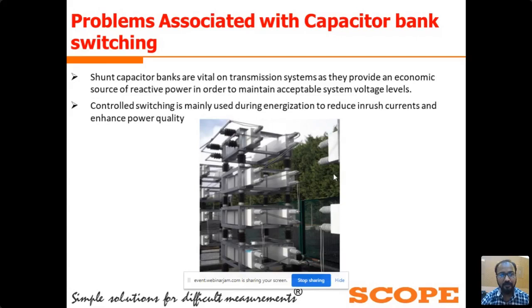During random energization of a capacitor bank, we have observed high inrush currents in the system. This type of high inrush current causes disturbance to the other connected systems, and also affects the power quality of the system. So to minimize this high inrush current during the energization of the capacitor bank, we are using the control switching device.